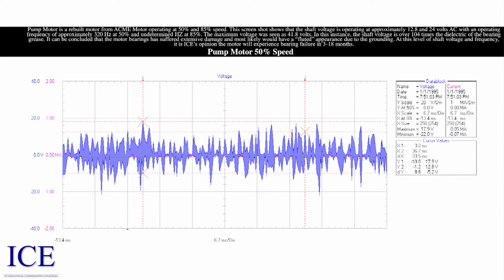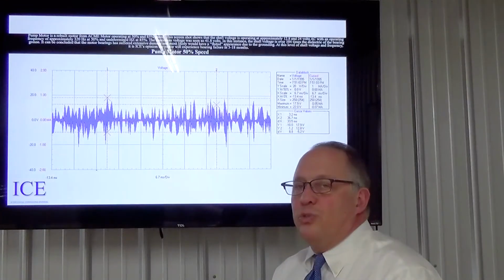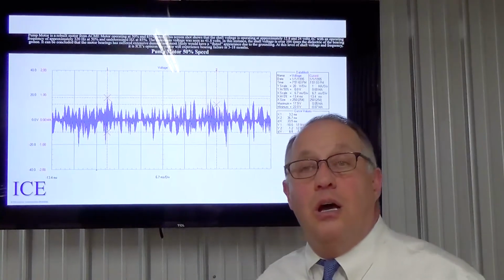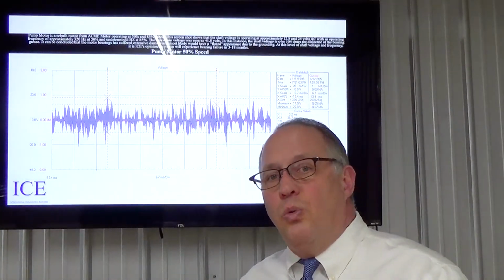In this particular case, this motor ended up being a rebuilt motor operating at 50 to 85% of the speed. It shows the shaft voltage operating at approximately 12.8 and 24 volts AC with an operating frequency of approximately 320 hertz at 50%, and at 85% the frequency was undetermined. So this particular one was at 50%, and you can see the voltage peak to peak was anywhere from 12 volts up to approximately 20 volts, and this was just when the motor was installed. It hadn't even been used for a very long time. We caught this one early.